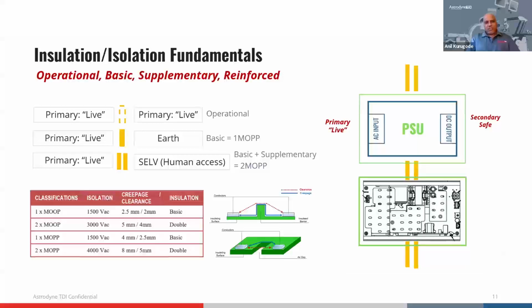But whenever a human is involved - as you see in the diagram, there's a primary circuit on this end, which is the wall power, and on the other side is the secondary, where the patient or operator can get connected - there we need two levels of protection, or two means of protection. This is also commonly called double insulation or reinforced insulation in the industry. The difference between the two is intuitive and logical: if one layer of insulation fails, the other should be sufficient to protect you.